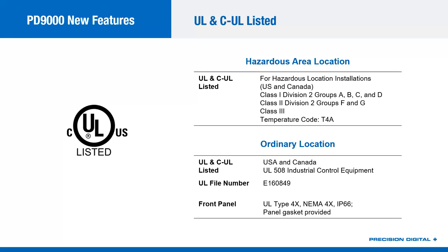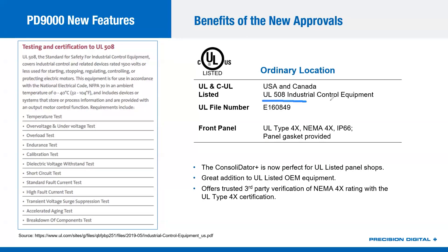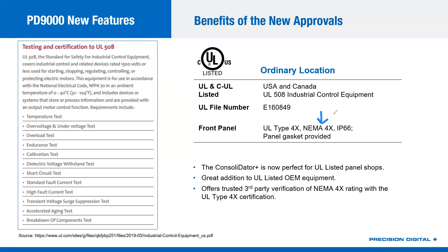The nice part about these approvals is that because it is UL 508 for industrial control equipment, it has passed a whole series of tests. A UL listed panel shop or skid can have this installed and it brings its UL approvals with it — they don't need a UL inspector to okay the product because it is already a complete UL listed product. UL has also given us their UL Type 4X rating, which is the same dust-tight, water-tight, corrosion-resistant approval as NEMA 4X, confirmed by third-party testing.